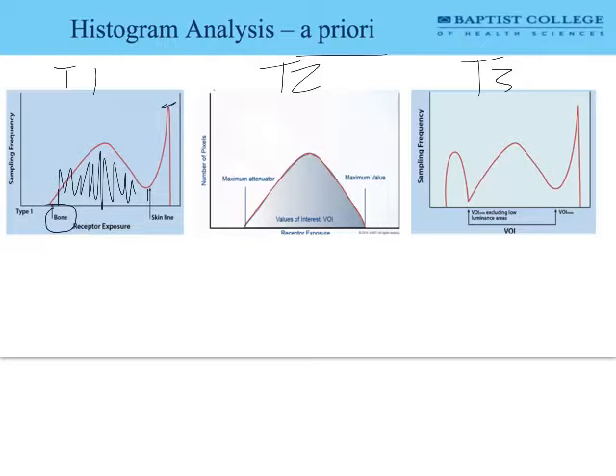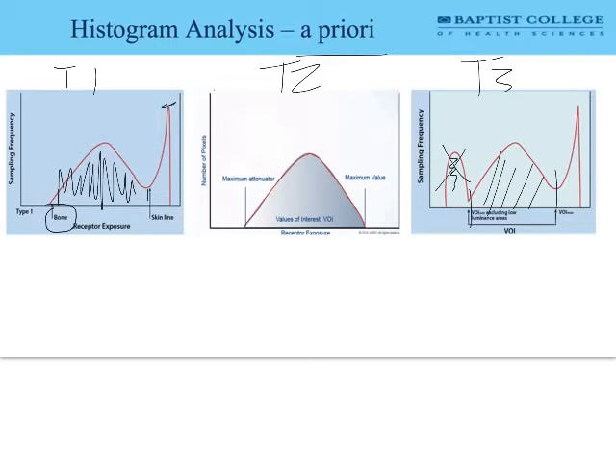Type 3 is helpful because it accounts for a significant attenuating object — such as metal or even barium — within the x-ray image, and tries to accommodate for that without changing the image values too much. It sets boundaries that exclude very dense objects like barium or a prosthetic hip. Anything beyond the volume minimum or above the upper threshold is excluded. The computer recognizes that the dense object is barium or a prosthetic hip and makes accommodations for it when analyzing the volume of interest.